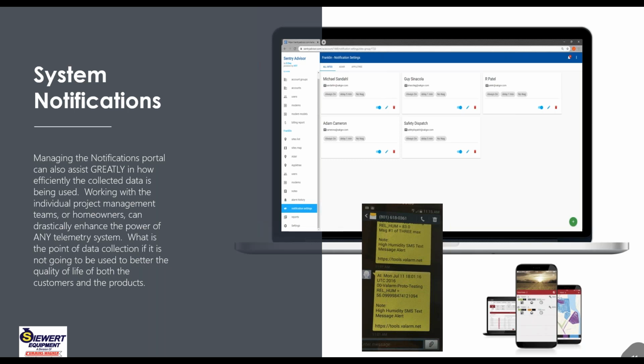If the alarm persisted and an operator hasn't acknowledged it, certain systems allow a nag feature, where the operator is re-messaged saying nobody has responded to this, I'm going to try you one more time. The nag also works as an escalation - if an operator doesn't respond, it can be escalated to the operator supervisor, who can then decide on who to dispatch or how to dispatch. So figuring out the management side, how to configure notifications to provide the biggest benefit to both you and your operators, as well as the most efficient response to whatever the alert was generated for.